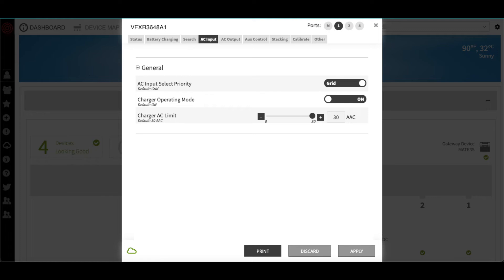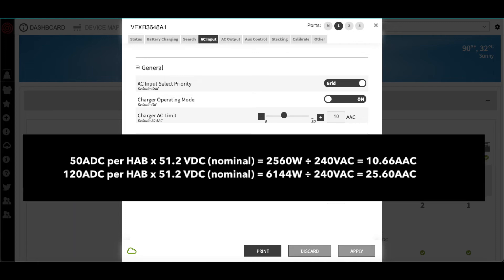The 10-year warranty allows for 50 amps of DC charging current per HAB, while the 7.5-year warranty allows for 120 amps of DC charging current per HAB. Outback only lets us set the AC input amp limit, which means we need to convert the allowable DC amps specified by the HAB warranty to AC amps in order to determine the proper set point.